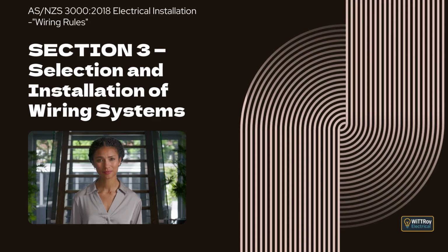At every joint in the cable sheath, and at all terminations, the continuity of the combined PEN conductor must be maintained, and this must be ensured by using a bonding conductor in addition to whatever sealing and clamping method is used on the external conductor. The resistance of this bonding conductor at joints must not be greater than the resistance of the cable sheath itself. At terminations, two separate conductors must be used, one for protective earthing and one for the neutral. The minimum size of the protective earthing conductor must comply with Clause 5.3.3 in Table 5.1, and the neutral conductor must be not less than 6 square millimeters, or comply with Clause 3.5.2.